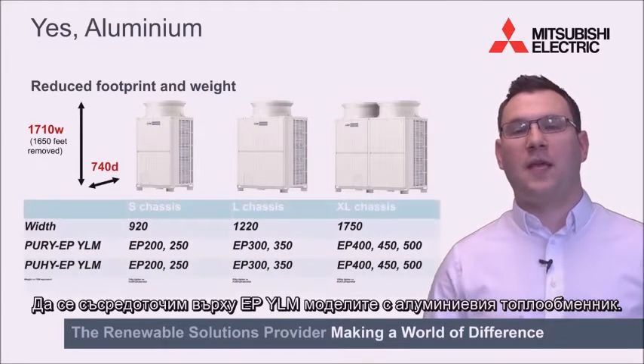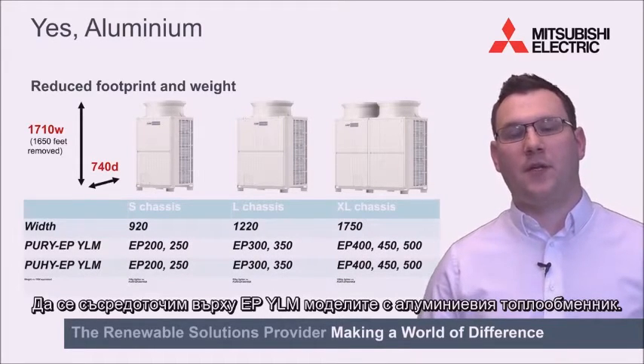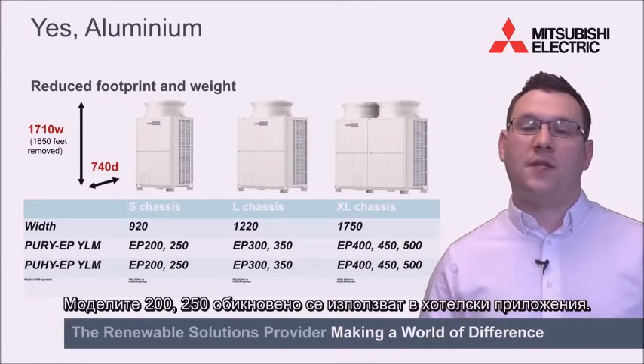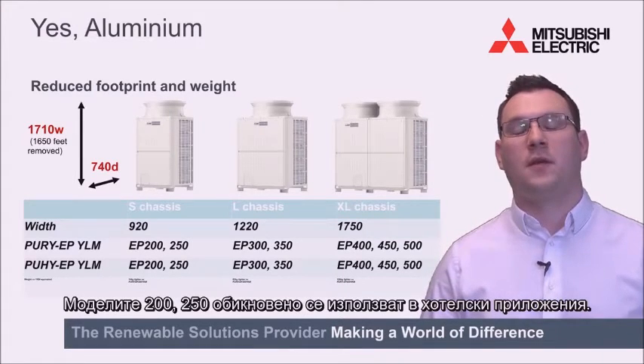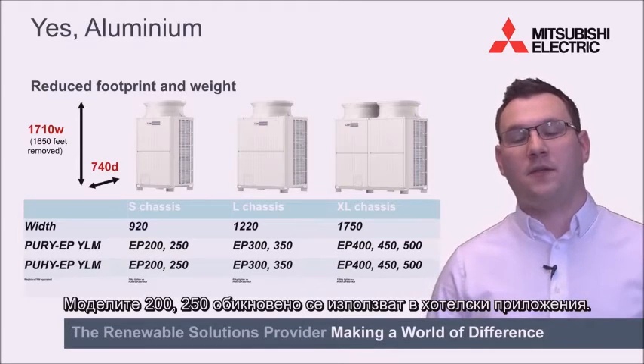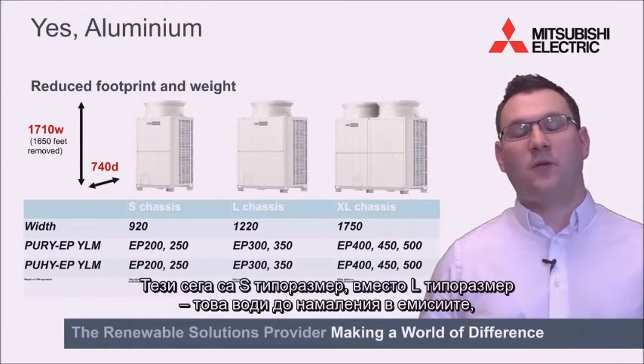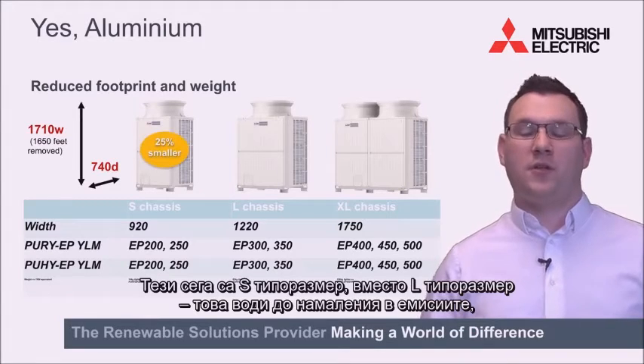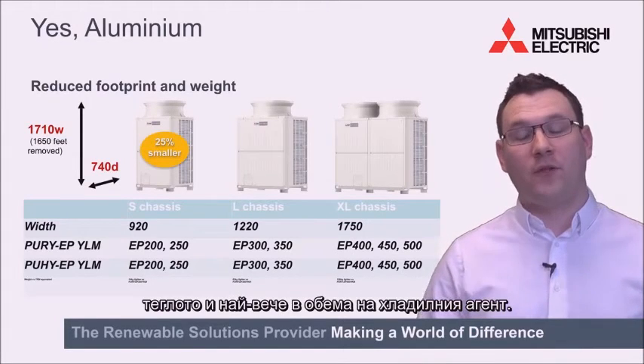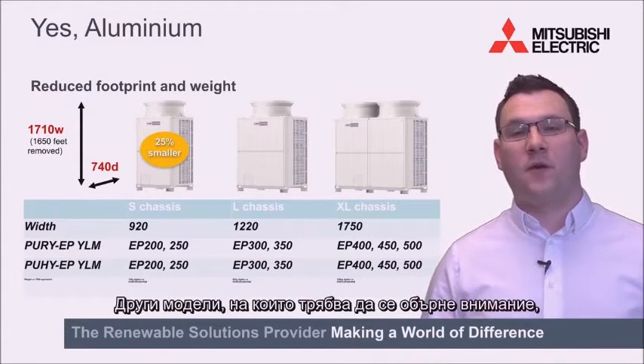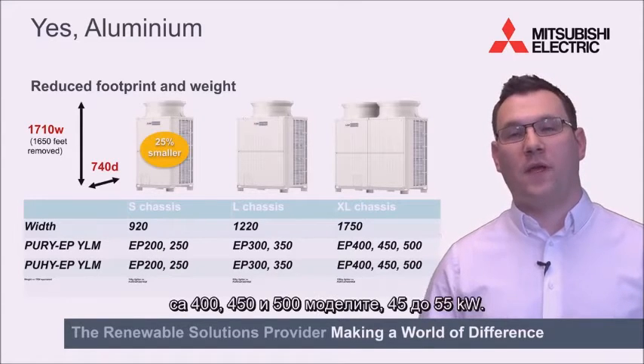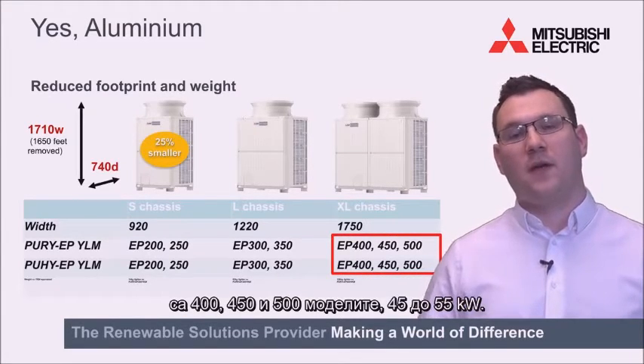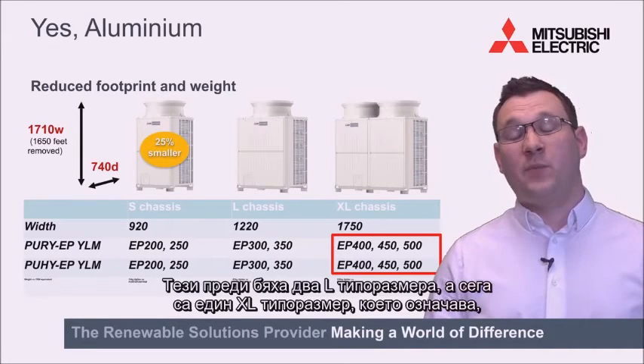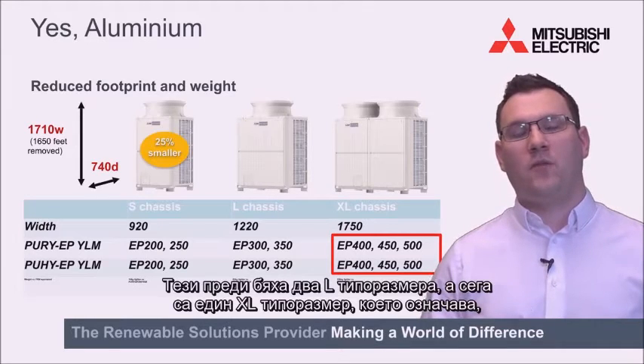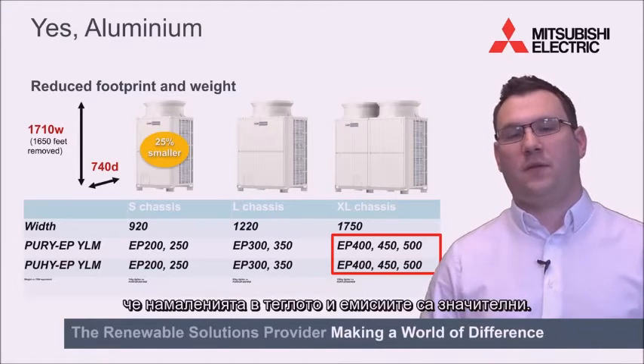So if we now focus on the EP YLM models with the aluminium heat exchanger, the 200 and 250, 22, 28 kilowatt models typically used in hotel applications. These have gone down from an L chassis to an S chassis, meaning reductions in footprint, weight and critically refrigerant volume. Another one to focus on are the 400, 450 and 500, so 45 to 55 kilowatts. These previously were two L chassis, now a single XL chassis, meaning the reductions in weight and footprint are significant.